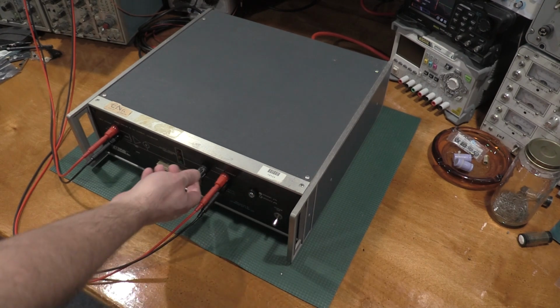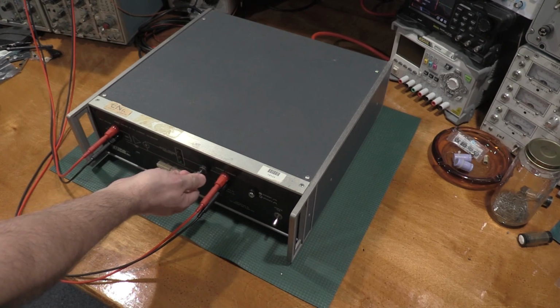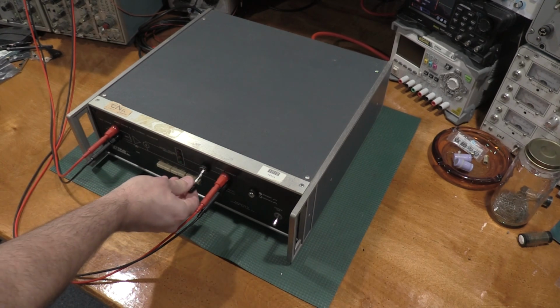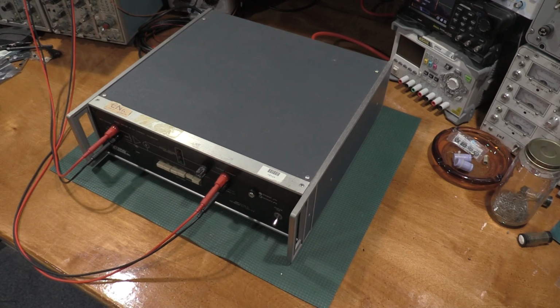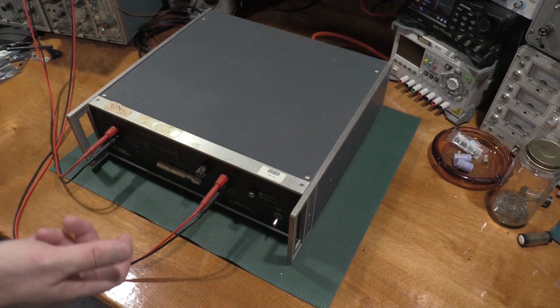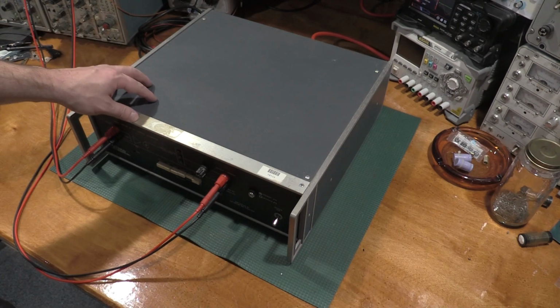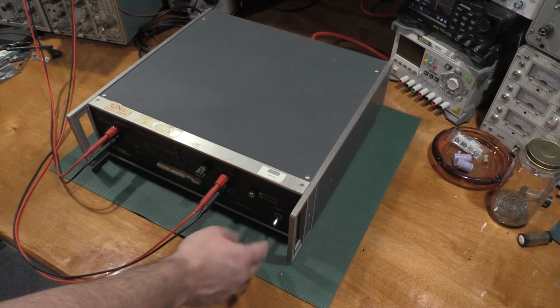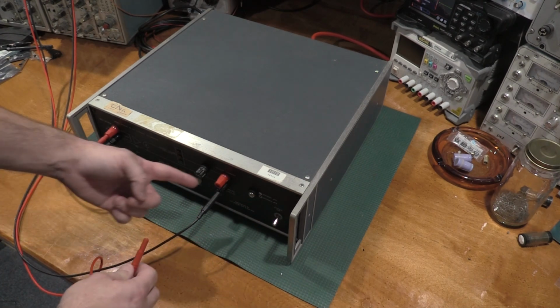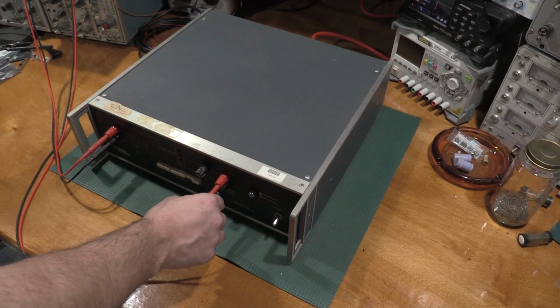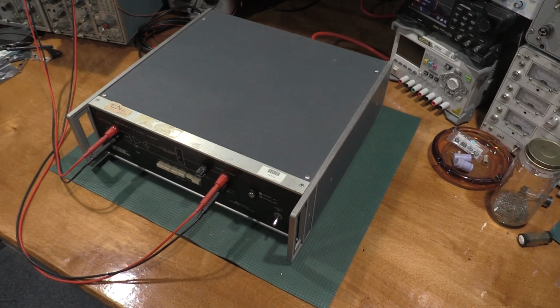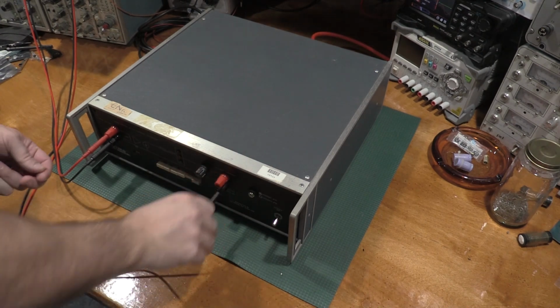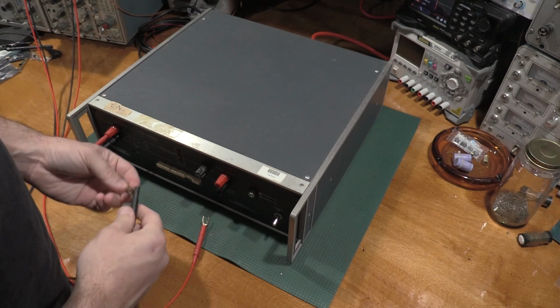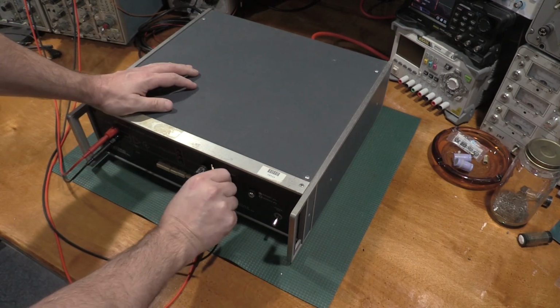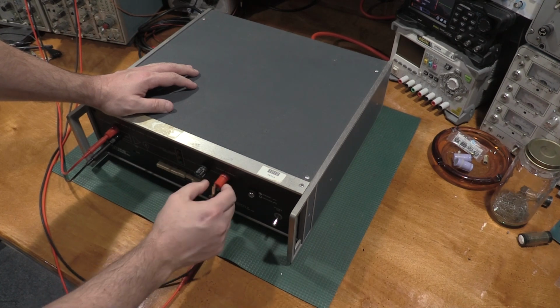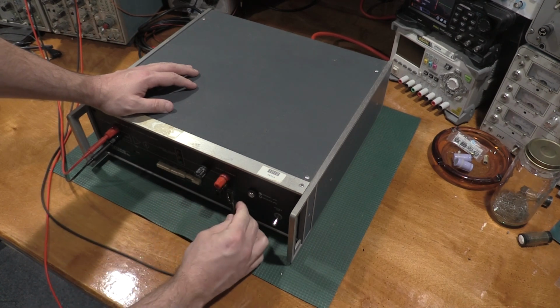One thing the manual does say on this unit is to make sure this is in standby mode before connecting and removing any load. That is to keep the compliance voltage from going to the moon, this being a true constant current source. If you unplug this, obviously the unit's off, it's in standby. If you unplug this, it's going to shoot the voltage at these terminals all the way to the rail to try to push current, which is what we don't want to do. Also, for the current side of things, I don't like how shallow these banana plugs are in those jacks, so we are going to get a bit better and chunkier connection to these current posts.